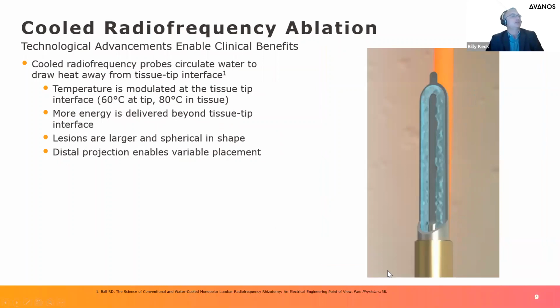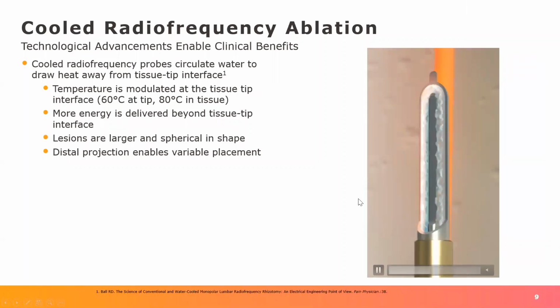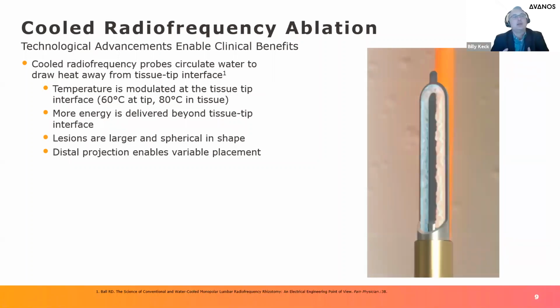With cooled radiofrequency ablation, what we've done is we've internally circulated water through the probe tip. By doing so, we're maintaining the temperature at that probe tip at 60 degrees. What that does is it prevents that charring effect from happening, so the char doesn't get built up where the tissue meets that probe tip.